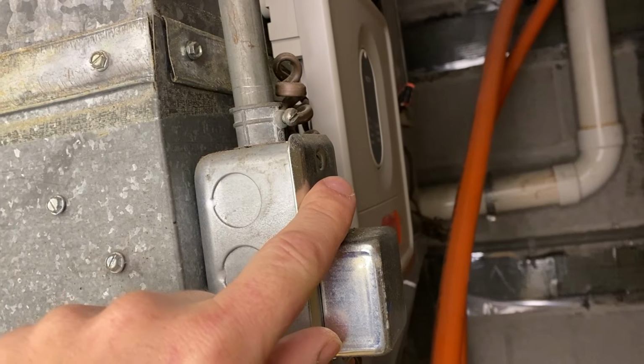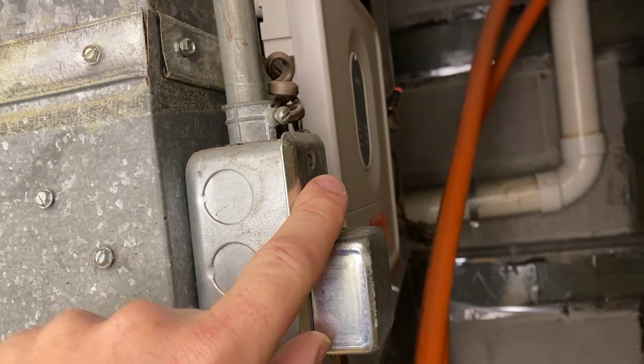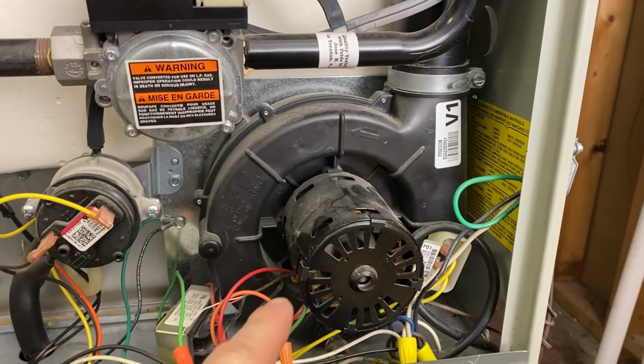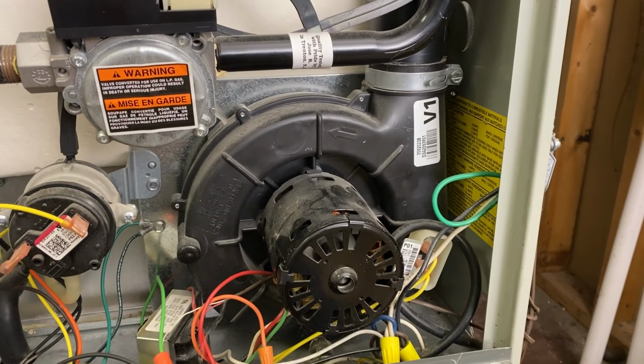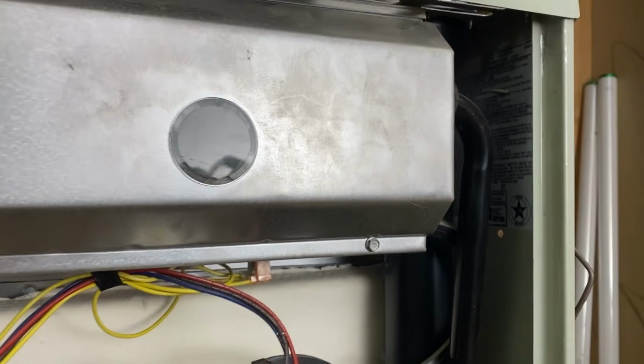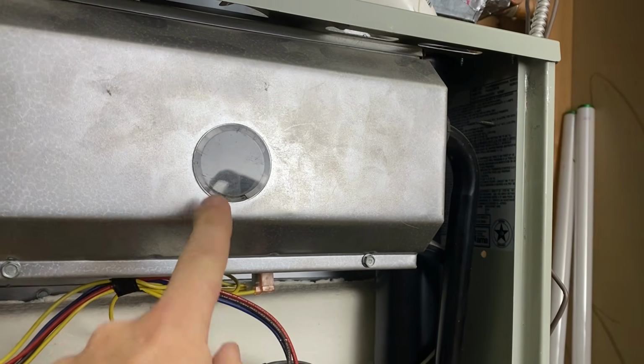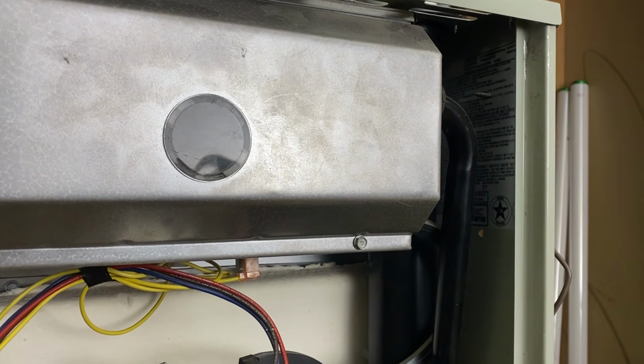So I'm going to turn the power back on, and then we're going to watch what happens. Okay, so you can hear the induced draft motor started, so that's inducing the draft. And then I'm going to look in here, you should see a glow. I heard the gas valve come on, and then I heard it shut off. And so we have no hot surface igniter glow in there, so we didn't see anything light up in here, and that's the problem that we're having.